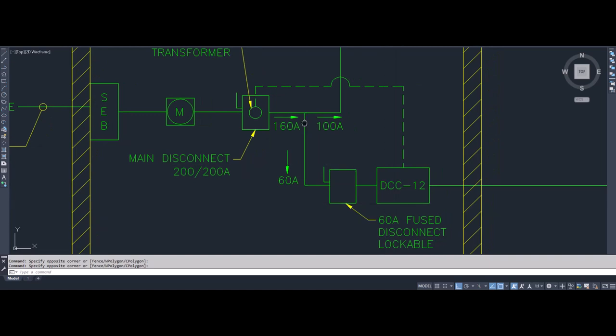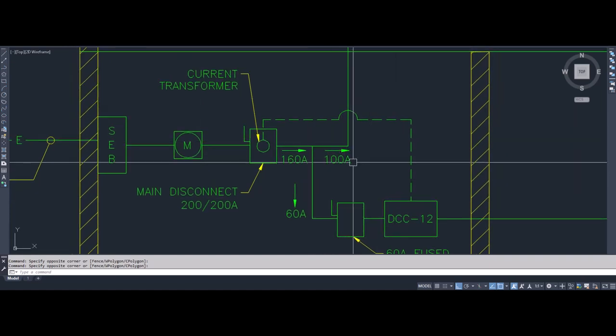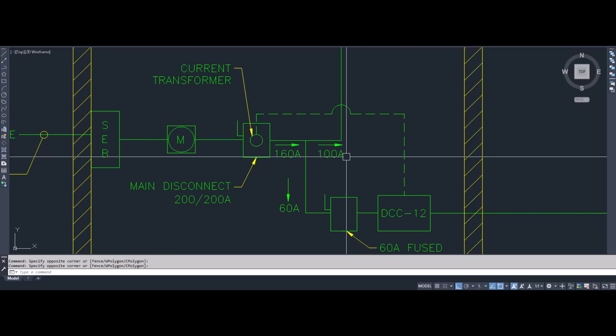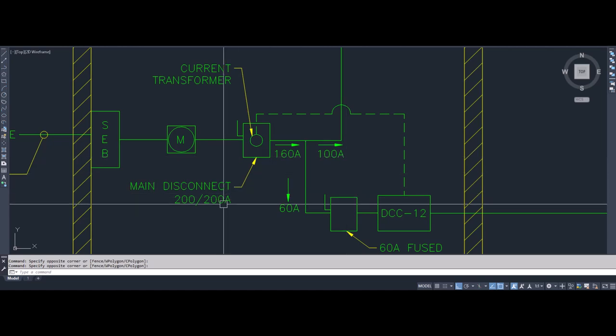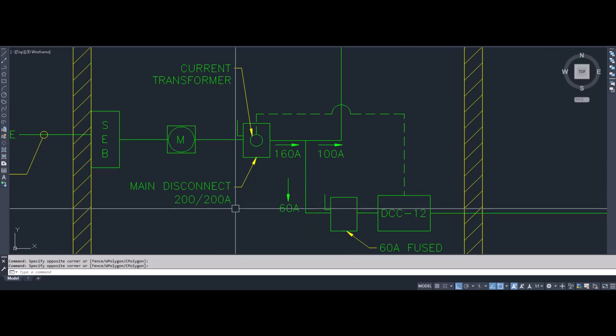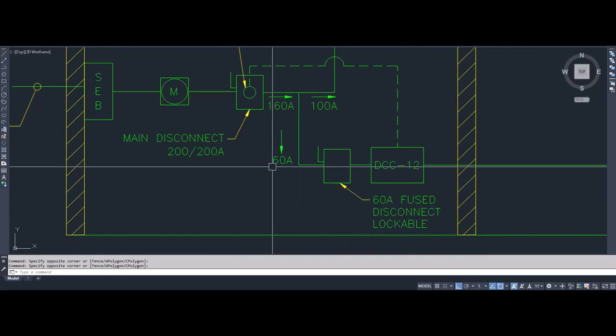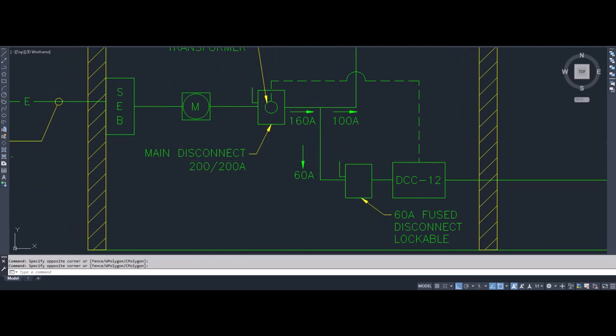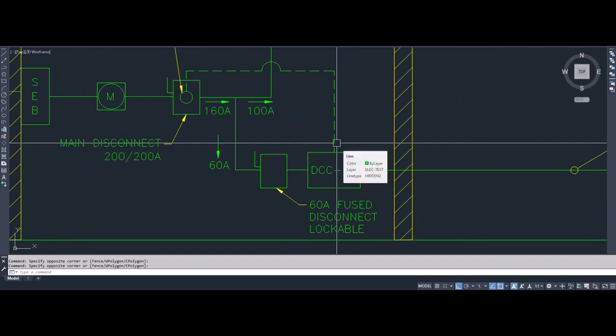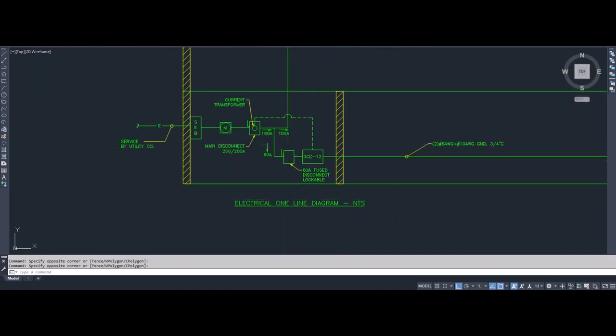The only time you need it is if during normal usage, such as in my case, I have an electric water heater, and with the AC system on full, so basically all the AC systems on, my load was somewhere around 160 or more. So with the EV charger at 60, I was exceeding the main disconnect. So in cases like that, these type of systems would be good to have. So you have to see if you actually need the system before you purchase and install one. So this is one case.